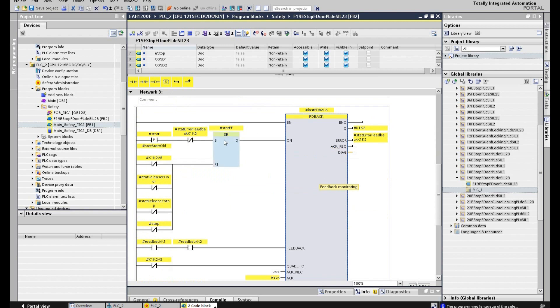But if you look at the detail of this safety logic, you'll find there's a start button here. The control logic is at the reset area — to enable or give an on signal, it relies on a start signal. It's a little bit odd to put all control logic at the reset area, and because all control conditions are at the reset area they must be negative logic. As I can see, most safety projects in a cell will not have specific start buttons, especially for the safety start.